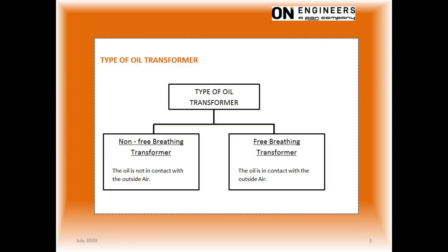When the transformer size gets larger, the non-breathing design has severe limitations. The free-breathing design will be more practical for larger transformers. In a free-breathing transformer, the oil is in contact with the outside air.